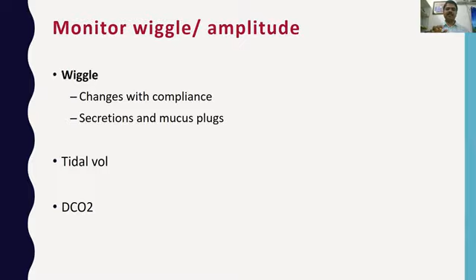So tidal volume of high frequency, that also you keep a constant monitoring. That should be noted in the monitoring sheet so that you know what is happening to the tidal volume in the high frequency. Usual desired tidal volume is around 2 ml per kg. So for a 1 kg baby it will be 2, for a 2 kg baby it will be 4. And another thing which you can monitor on the ventilator screen is DCO2.